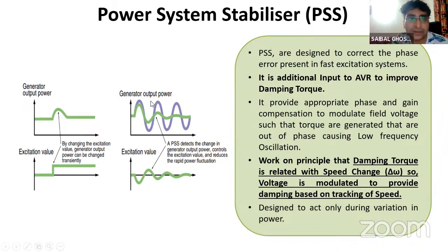Even though we do this modulation of excitation voltage based on the power output, in the sensing and taking action there will be some delay. In any closed loop, this delay may cause instability issues, or the gain is limited by this delay. The amount of action that can be taken is limited by this delay. But if you can predict this accurately using the accelerating power or accelerating torque, then you can take some advanced action, and based on that, the effectiveness of the PSS will improve.